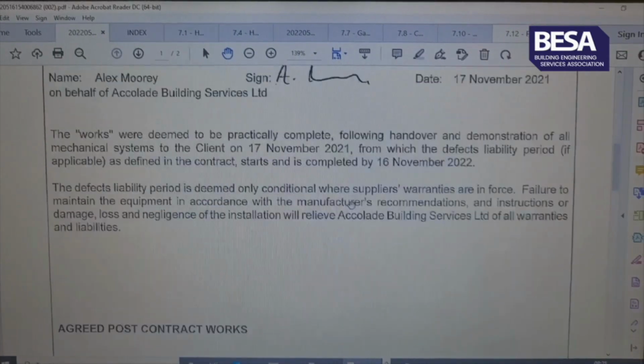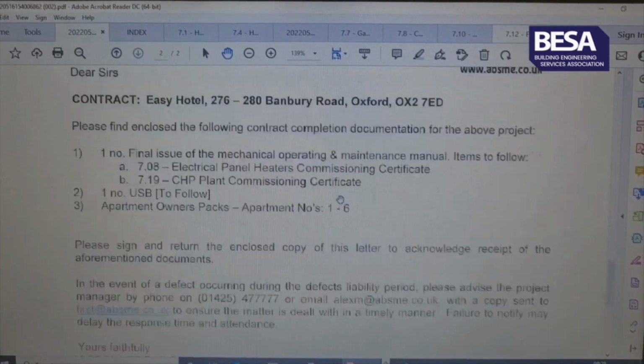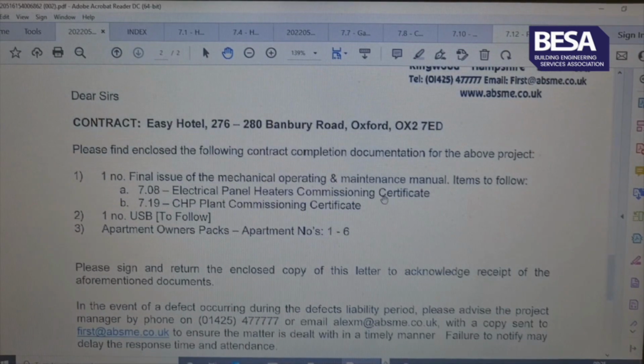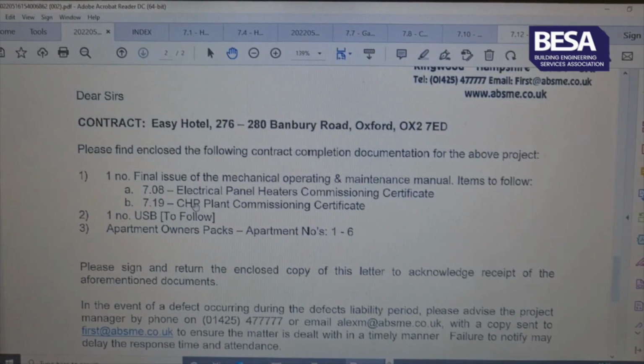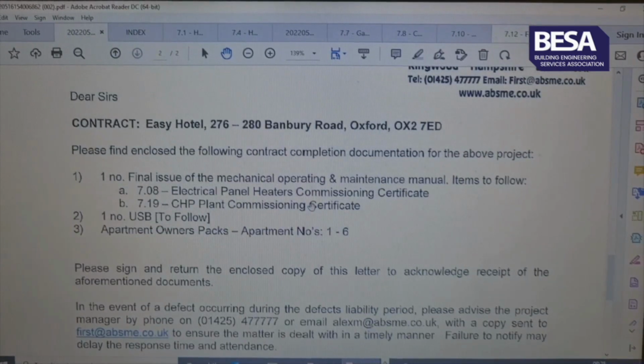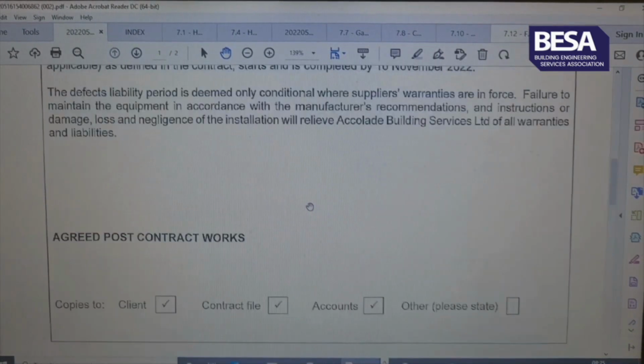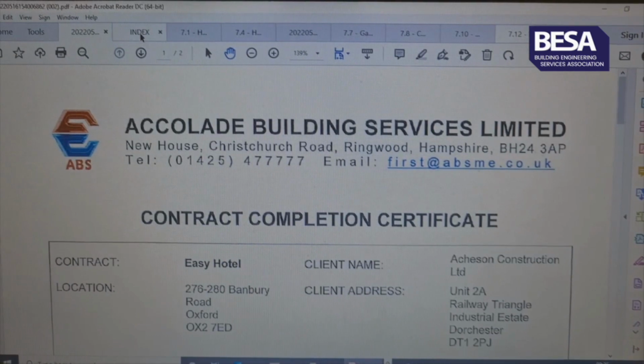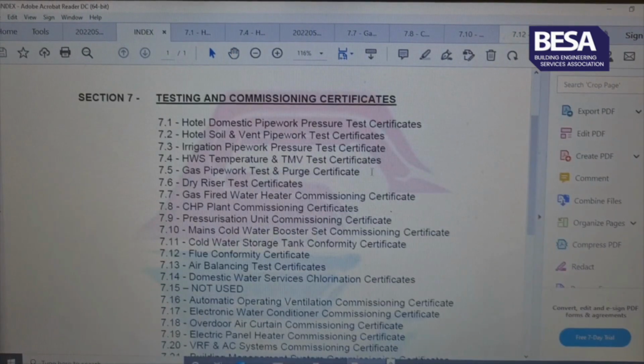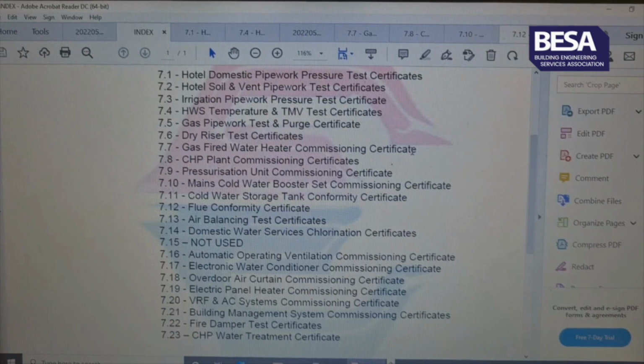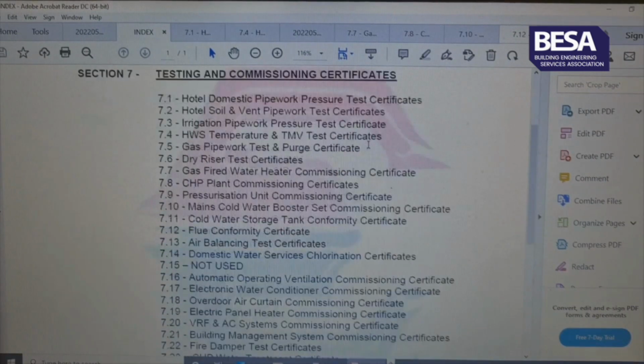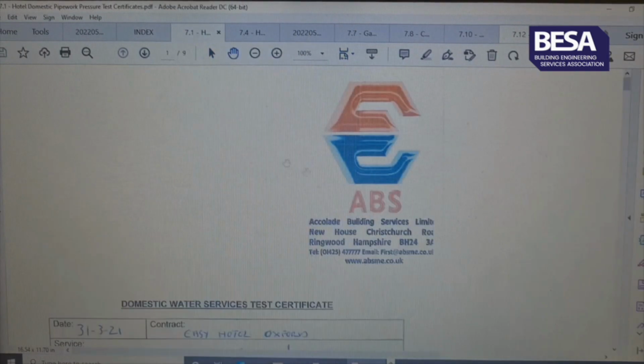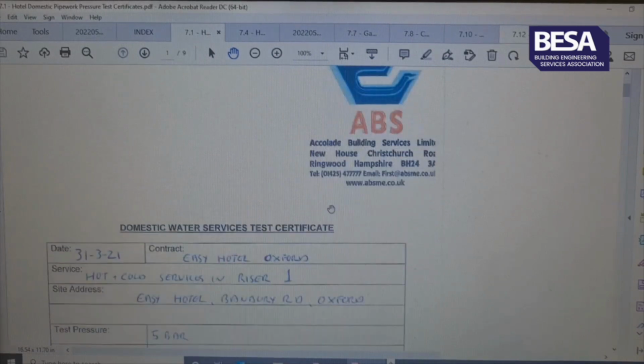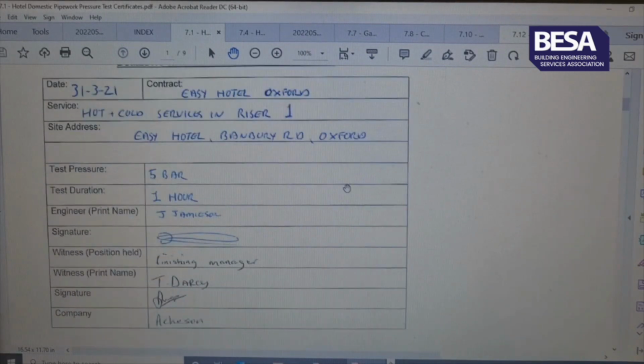When this was handed over, you'll see there were actually a couple of items outstanding. One being the panel heaters. We had a couple that were faulty that have been rectified, and the CHP plant, we had no permanent power in the building, so that was actually commissioned in the early part of this year, 2022. So again, that's our index, which I just showed you, a full set of test sheets there. And as I said, I'll go to the relevant ones, the test sheets associated with the hot water and heating, or domestics. So there's a section for domestic water pressure testing certificates.